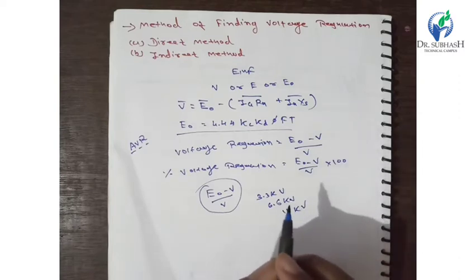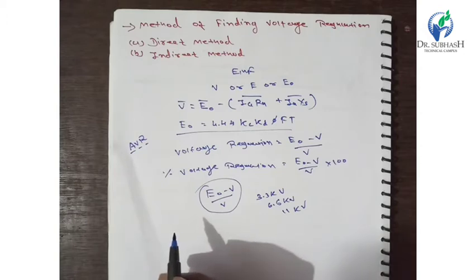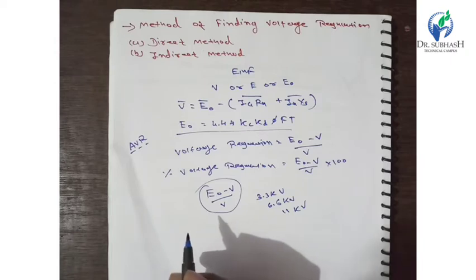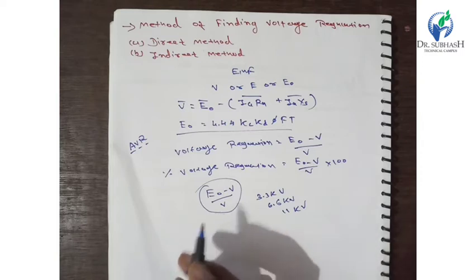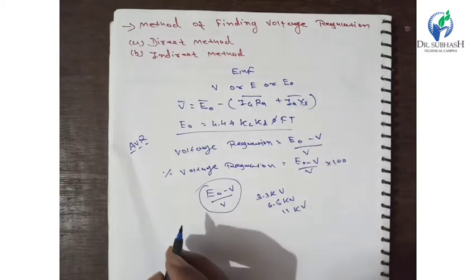So the insulation of armature winding is a critical factor. The load connected to the power system operates at a lagging power factor, and the load on the alternator varies frequently. The maximum variation will be from full load to no load condition. So, if the alternator at full load is suddenly thrown off, the terminal voltage rises suddenly. The insulation will break due to the voltage rise.